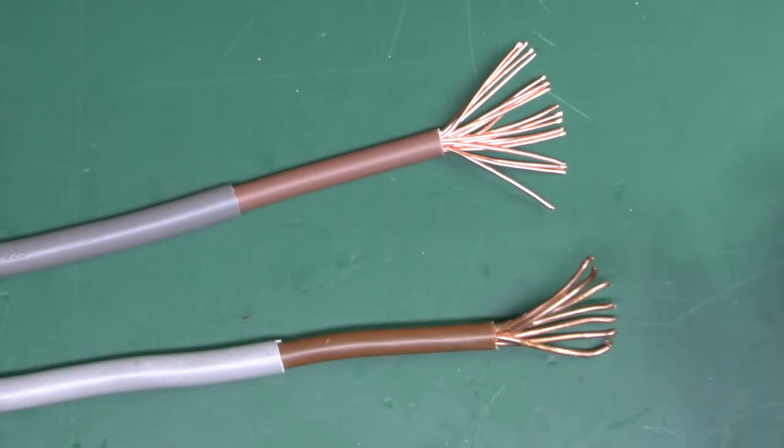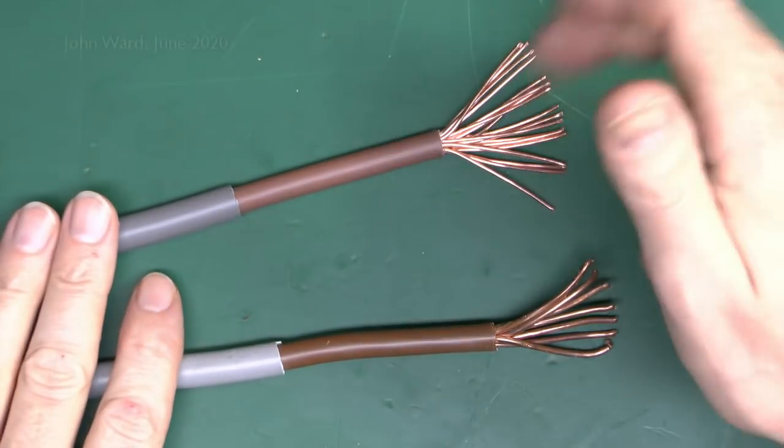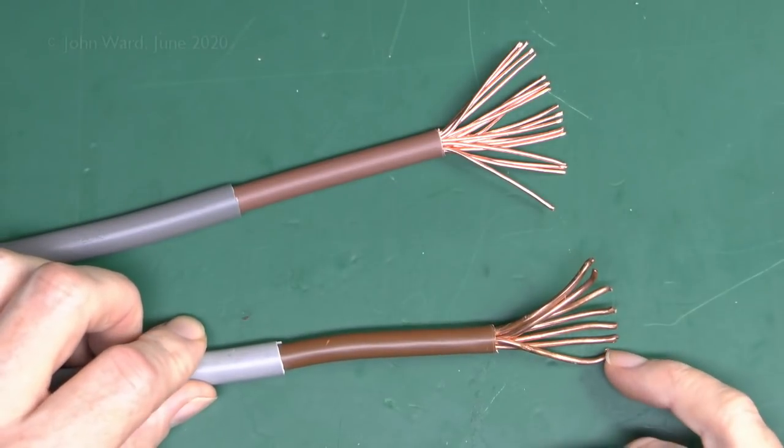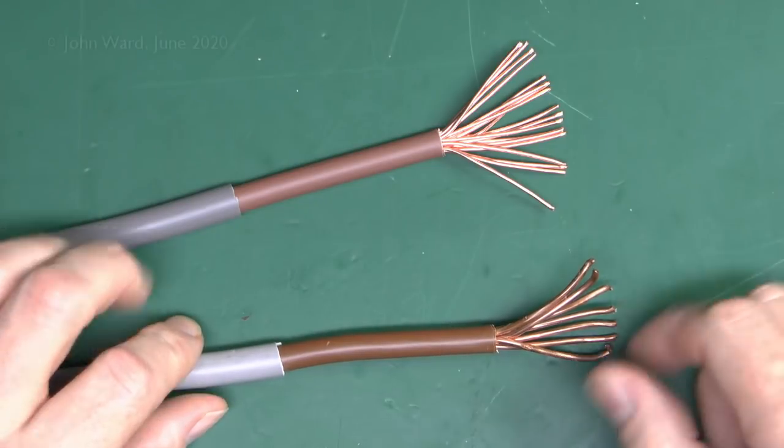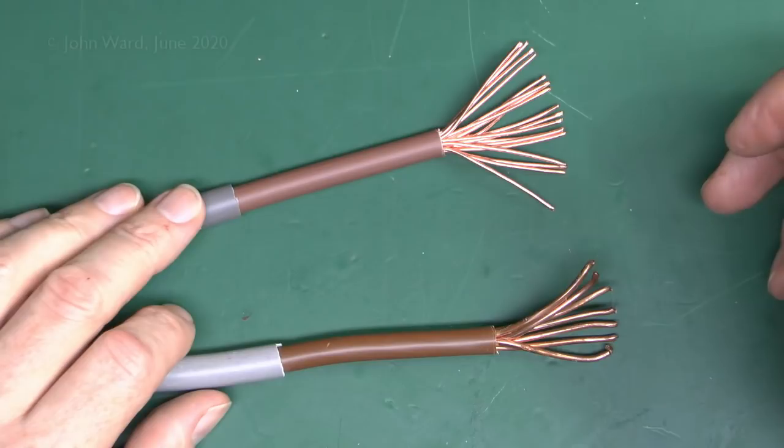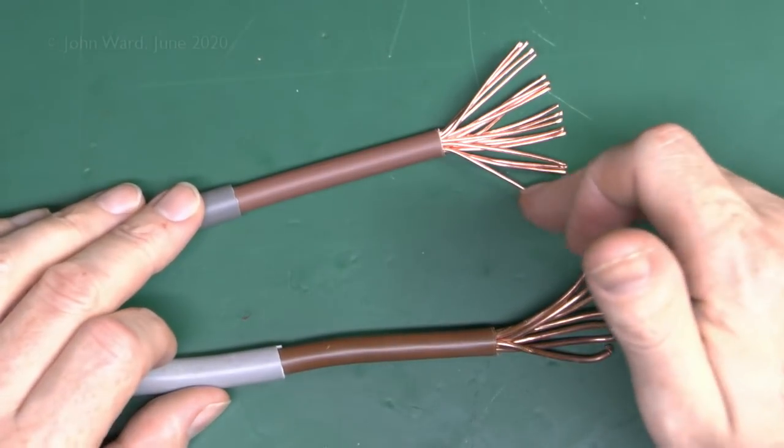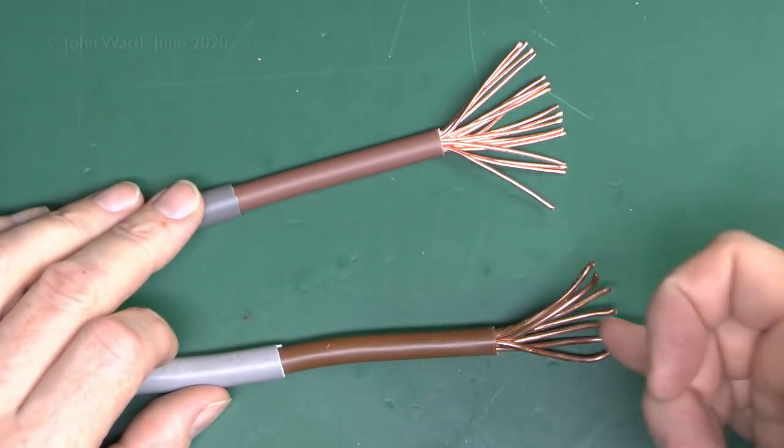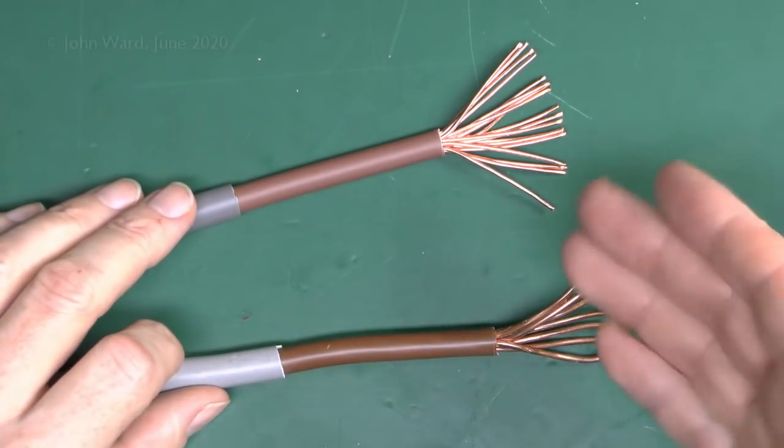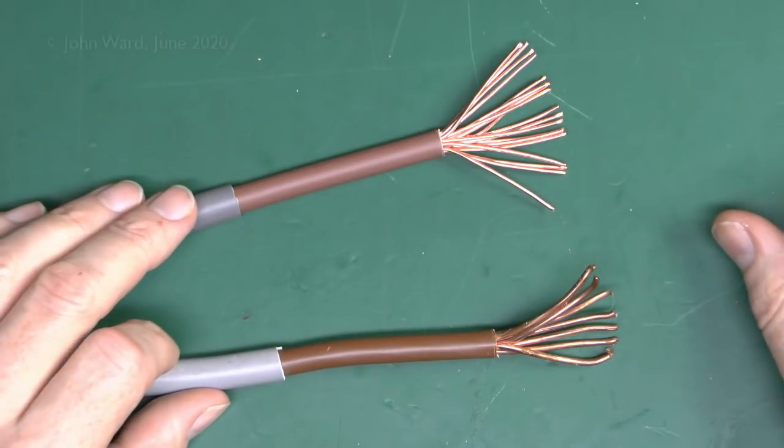Now just spread out these strands at the end of these two. This is far longer than you would strip them in normal use, but we can see here that this one only has seven individual strands within, whereas this one has considerably more. There's actually 19 in this one. So these are actually thinner strands, but there's more of them. These are thicker and there's less of them, so in total they both add up to 2.5mm², which of course is what you've actually paid for.